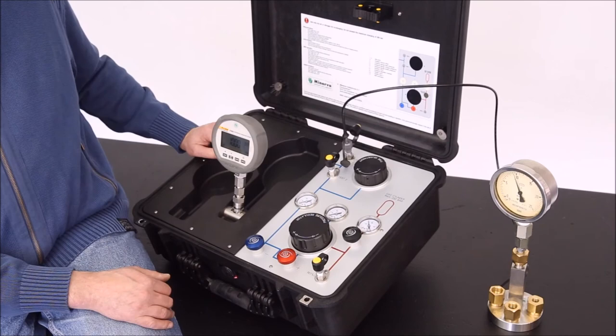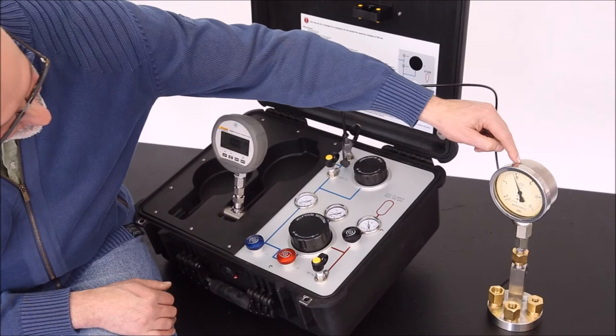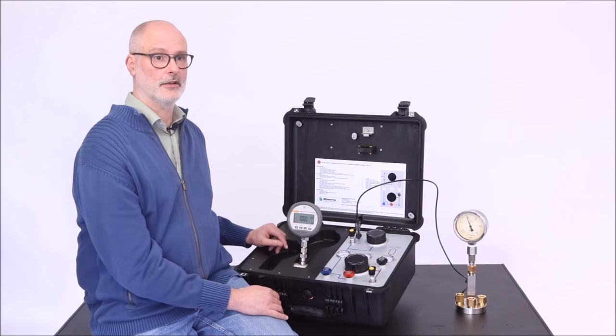So here we are, exactly 10 bars. And we can look at the device under test and compare it with my reference pressure. So this is the way to perform calibrations and set points.